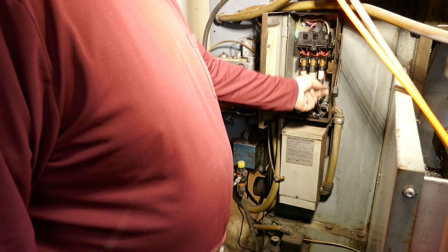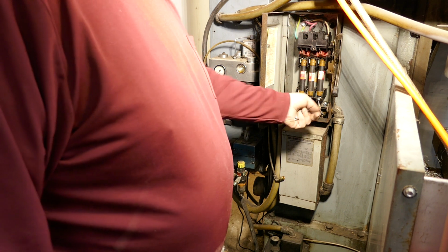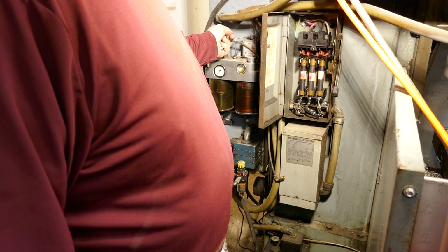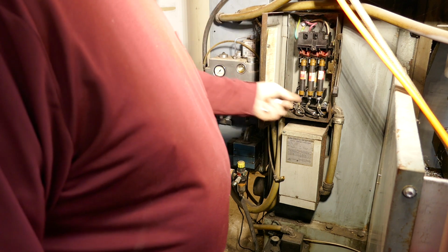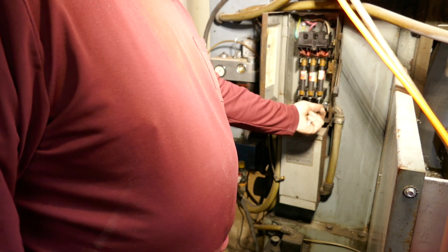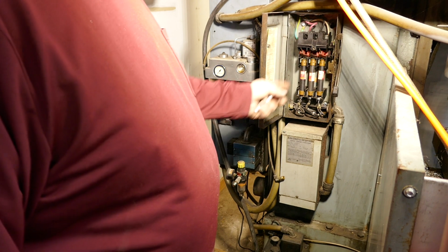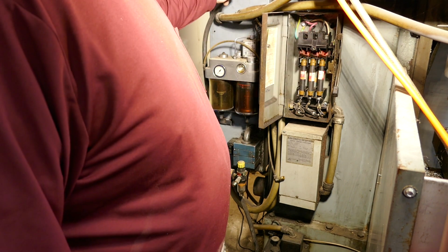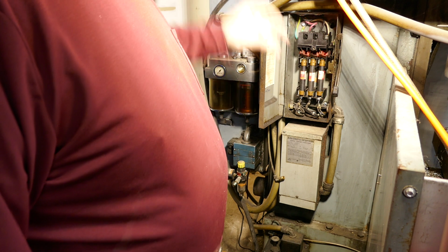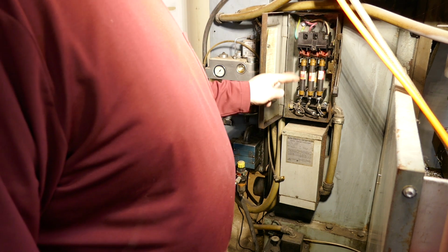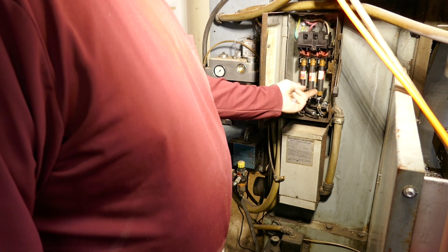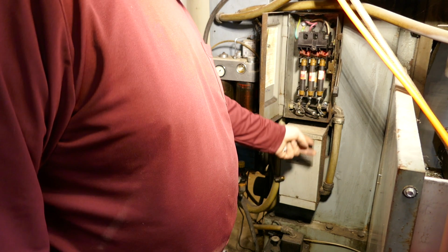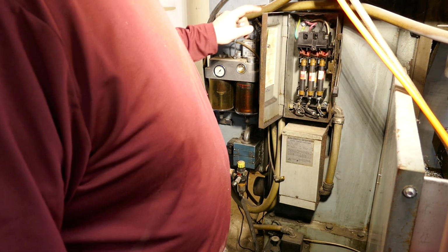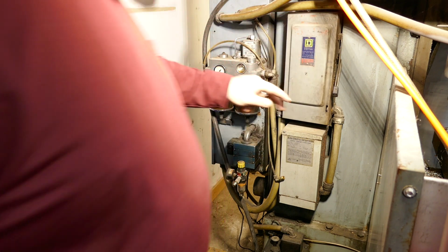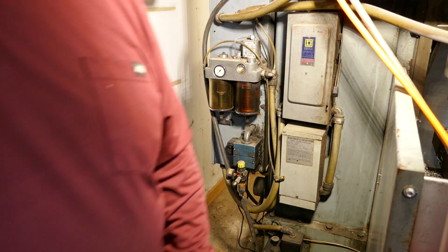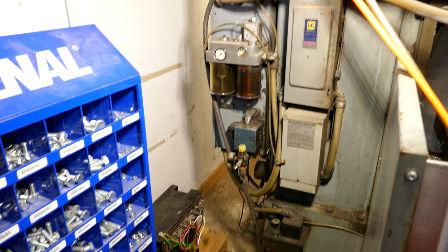And then I want the generated phase, which is number 2, to only go to the spindle drive assembly. So the generated phase, or the wild leg, high leg, whatever you want to call it, is going to be headed only to the spindle drive, and then the utility phase, which I consider better regulated, those two phases are going to this transformer and then to all the electronics. So that's my plan. Let me bring you down here and show you what I did for the connection.